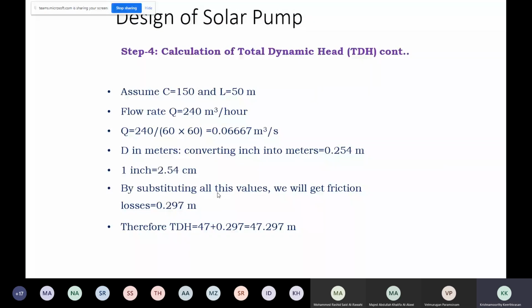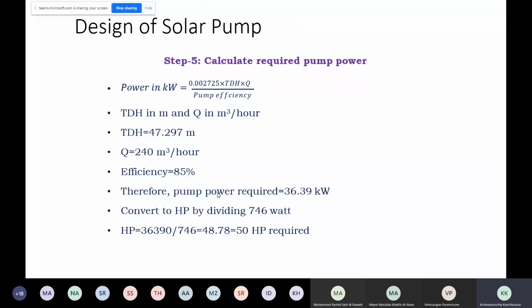And this is a simple calculation: power in kilowatt, a standard formula 0.002725, and TDH we calculated 47.297 meters, Q discharge 240 something. Pump efficiency, you see the efficiency here, this is more important. If you go for a good efficiency pump, your power requirement will be less. If you go for a low efficiency pump, your power requirement will be more. Using this formula, I found the kilowatt requirement is 36.39. 36,390 divided by 746 will give you HP, because when we go for purchasing pumps, they are rated in horsepower. Approximately 50 horsepower pump is required.